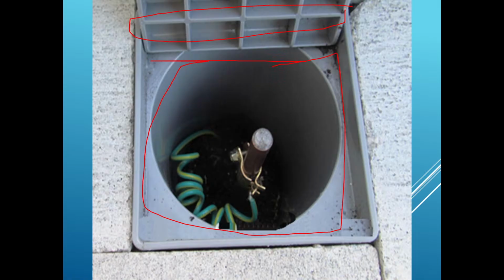The depth of this pit usually depends upon the resistivity of the soil. The only disadvantage of this method is the discontinuity of the earth wire from the earthing plate, which is placed below the ground, as it cannot be observed physically. Since the ground wire cannot be observed physically, it may cause misleading results and heavy loss under fault conditions because the earth wire is not visible. Therefore, if faults occur, we may not be able to predict that. So this is about the plate earthing.